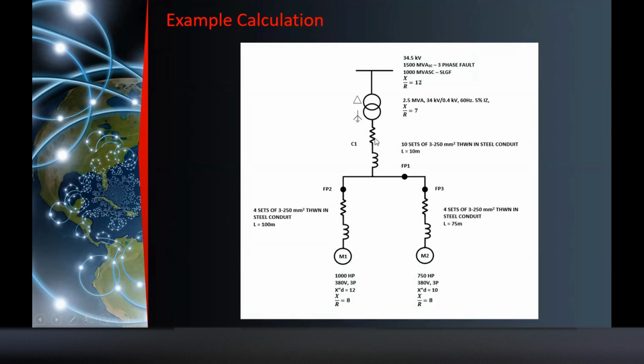So for this example, I have cable 1. I have 10 sets of 250 mm THWN in steel conduit, and the length is 10 meters. Okay? I have cable 2, 4 sets of 3-250, but the length is 100 meters. And I have 4 sets on the other feeder, 4 sets of 3-250 also, but 75 meters.